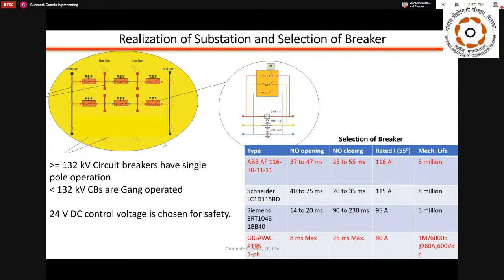Another point that needs to be looked at is that any breaker has to work within maybe 2-3 cycles. So you need to choose something which works as a breaker. We have to look at contactors which can give timings the same as a real breaker. So we looked at different ABB contactors, 3-phase contactors. We looked at Schneider and Siemens 3-phase contactors, different varieties, and then finally narrowed down to this 116 amp ABB contactor, which has closing and opening times well within 3 cycles of operation of our system. So this is something we have used.